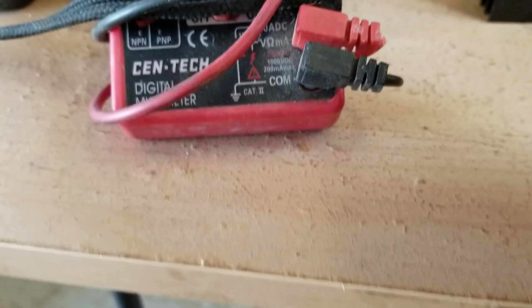On your AC voltage, when you set on AC voltage, again you always want to make sure you set higher than the voltage you're going to check. So if you're checking 120 volt outlets, you can stay on 200. But if you're checking 240 volt outlets, you've got to go up to 750 volts because 200 will not handle 240. That just makes sense, right?